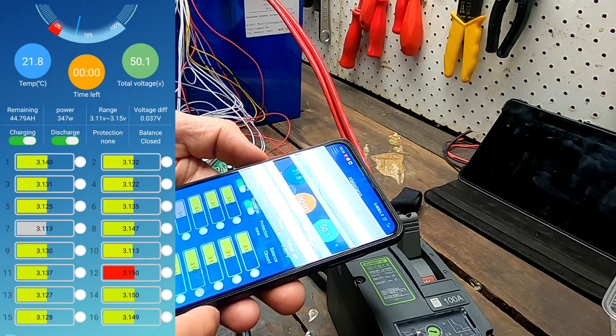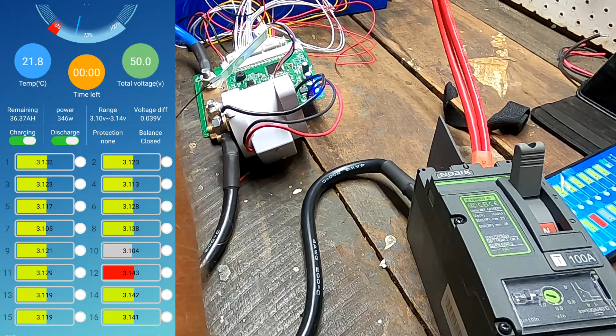As soon as the first cell hits 3.1, the relay should turn off. There we go, cell number 7, cell number 10. Which cell will make it, number 7 or number 10? There we go, 3.1 volts, turned off. BMS turned off. We have reached low voltage disconnect as programmed.